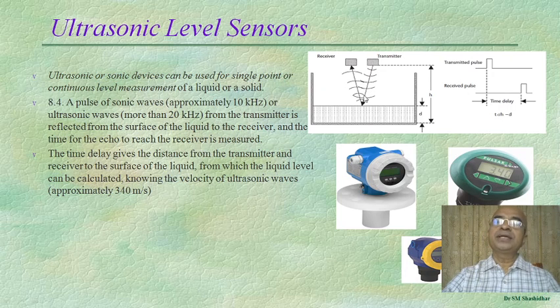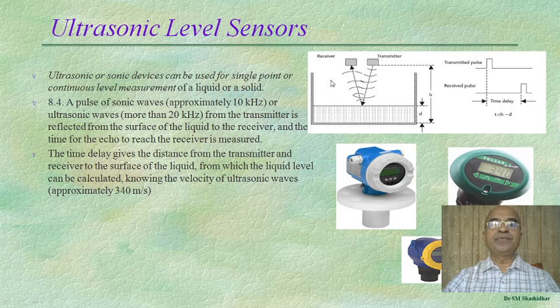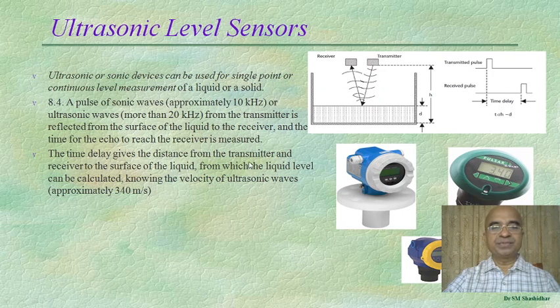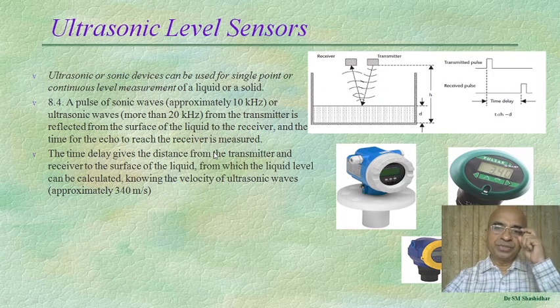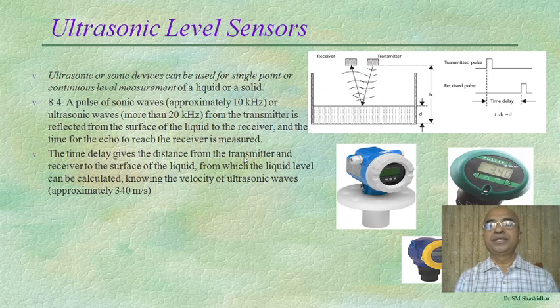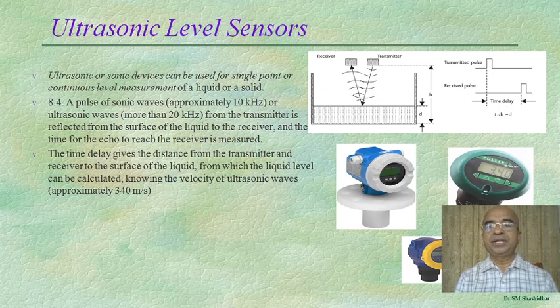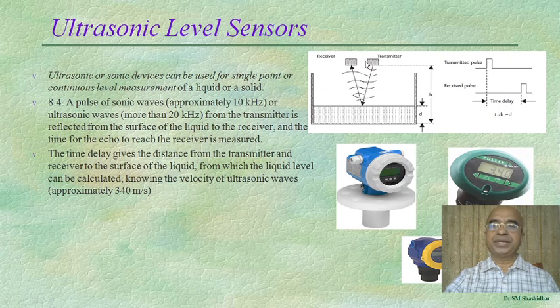The greater the time delay, the lower the level of liquid in the tank; the smaller the time delay, the higher the liquid level. The time delay gives the distance from the transmitter to the surface of the liquid. Knowing the velocity of ultrasonic waves — approximately 340 meters per second — an automated system calculates and displays the liquid level.